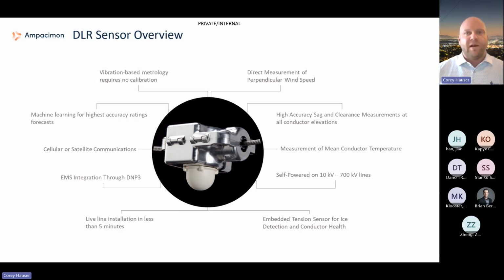It is self-powered, inductively powered from the line, from 10 kV up to about 800 kV, so we can put this on really any line you may have out there. We talked about the embedded tension sensor for ice and potential galloping. Installation can be done live line or during an outage, either via helicopter or bucket truck, or in the very near future we will have our drone-deployable sensor released.